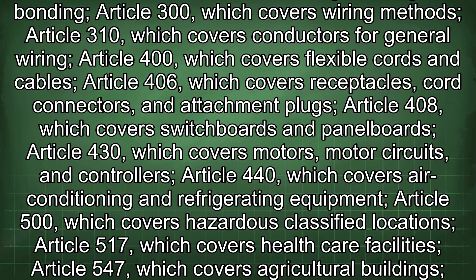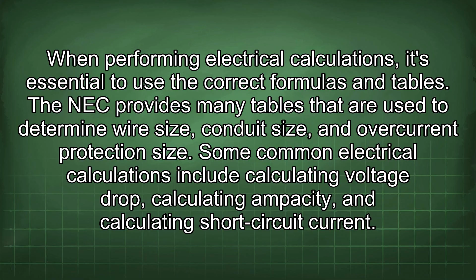When performing electrical calculations, it's essential to use the correct formulas and tables. The NEC provides many tables that are used to determine wire size, conduit size, and overcurrent protection size. Some common electrical calculations include calculating voltage drop, calculating ampacity, and calculating short circuit current.